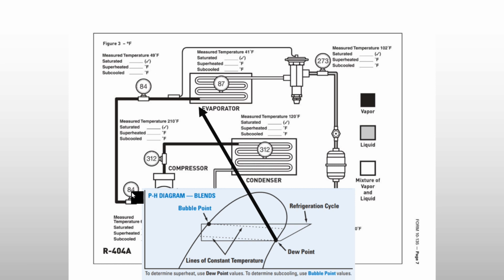I'm going to use the dew point on the outlet of the evaporator to know what my TXV superheat is. I'm going to use dew point on my inlet to my compressor so I know what total superheat is back to the compressor. And I'm going to use dew point on my compressor discharge so I know what the superheat of the compressor discharge is. All going to be used with the black dew point, also known as on the PT chart from Sporlan.